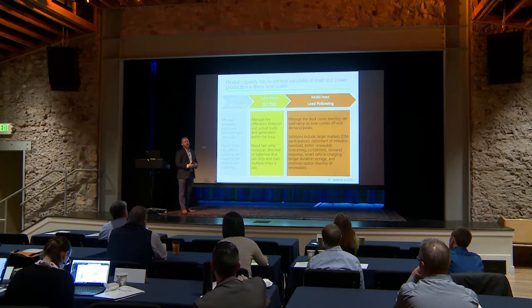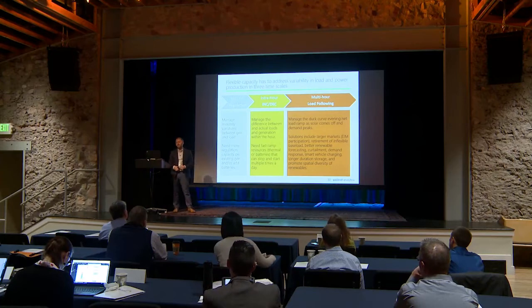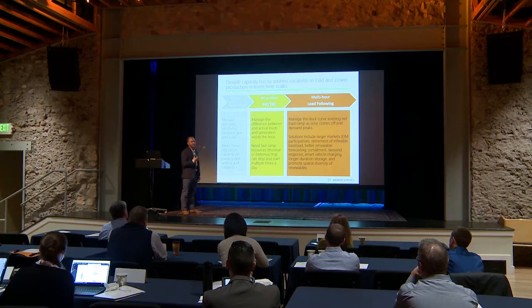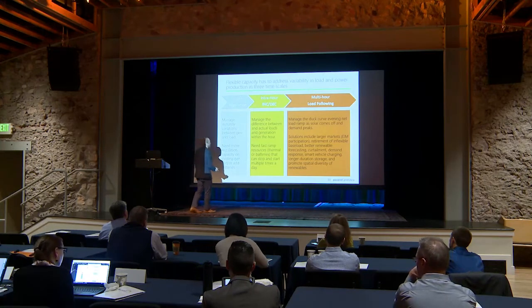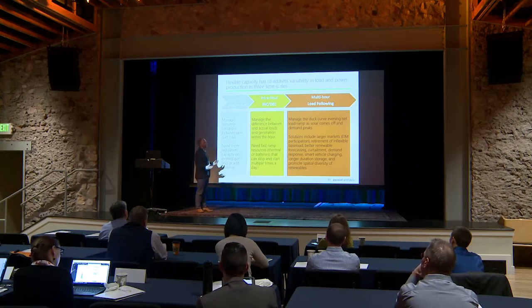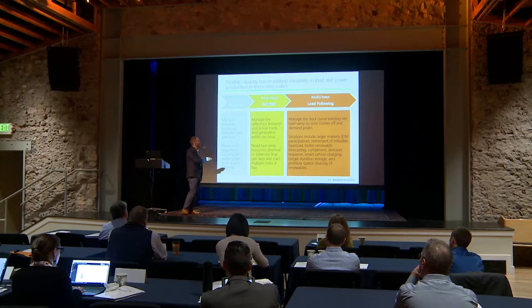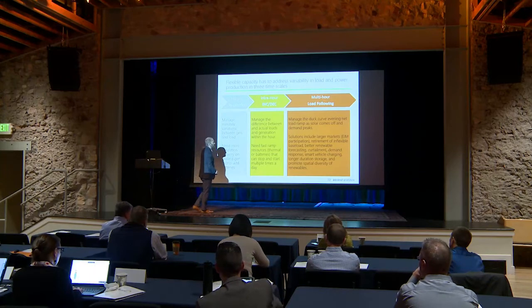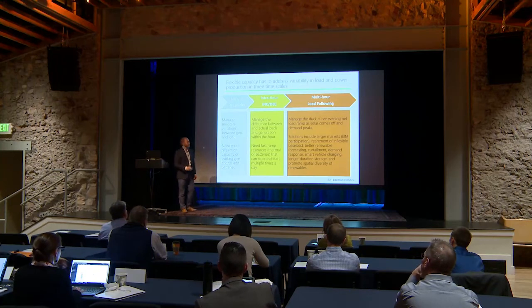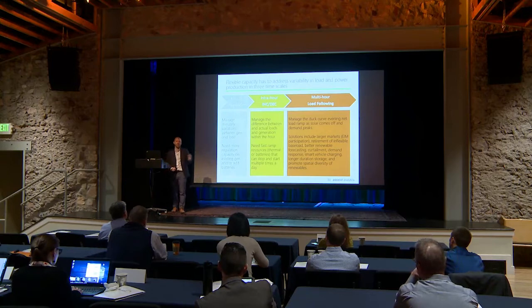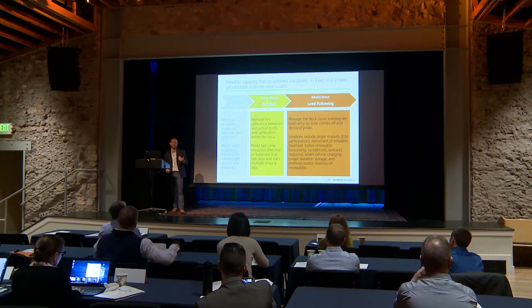Third, multi-hour flexibility at one to four hours — what we call load following: having enough resources to meet increasing load. Options include bigger markets with more resource diversity, retiring inflexible baseload, better renewable forecasting, and curtailment. We find the most binding constraint in terms of flexibility is intra-hour — the ability for your units to ramp up very quickly in that 15-minute timescale to get system frequency back to the right range.